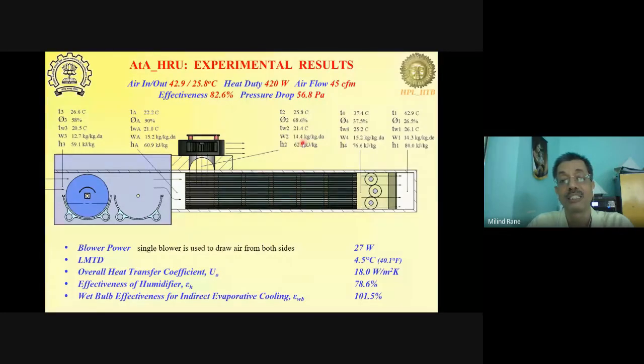Because here the humidity is 12.7 grams per kg of dry air, and here the outgoing air is 14.4 after it has picked up humidity from the activities of the people working in the space. So obviously this has to be reduced below this value using some other technique, like liquid desiccants, which could be solar regenerated, or conventional air conditioning units could be used just to dehumidify this particular cooled air.